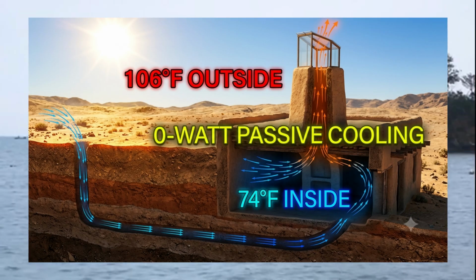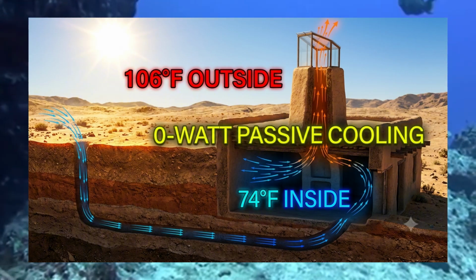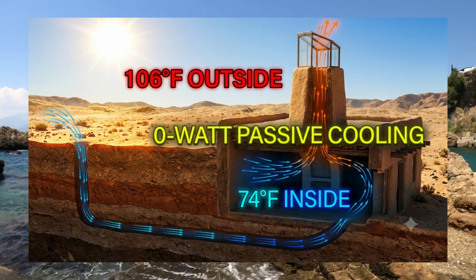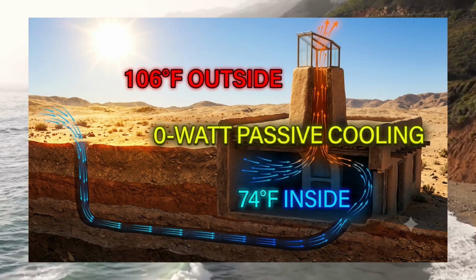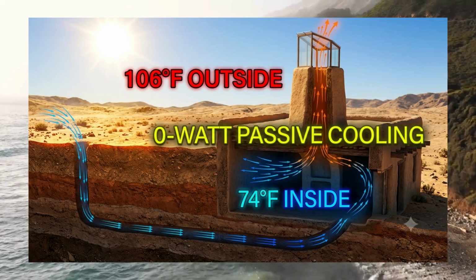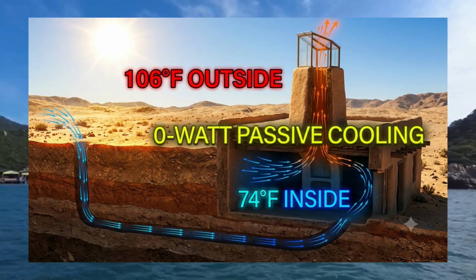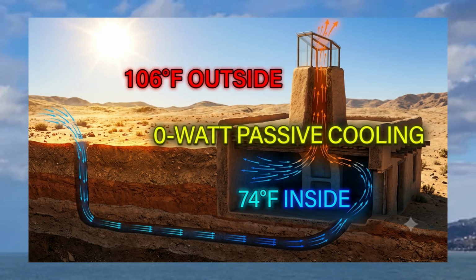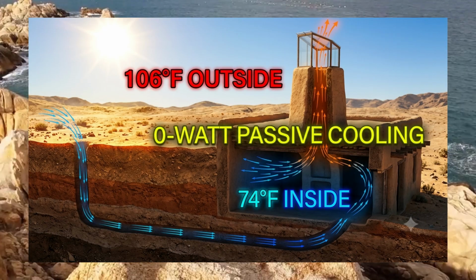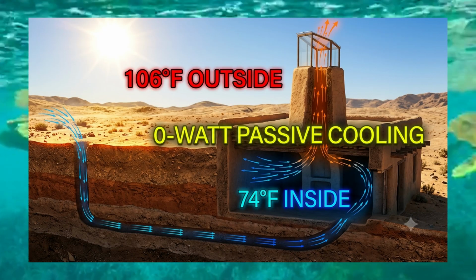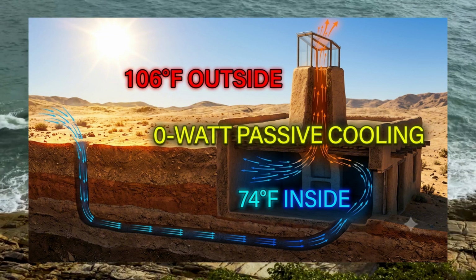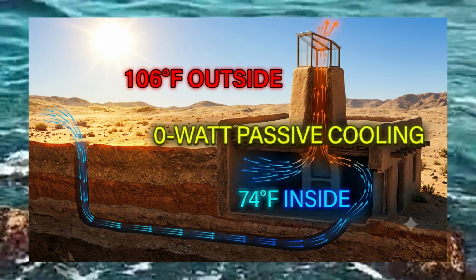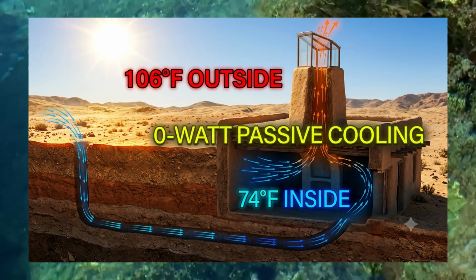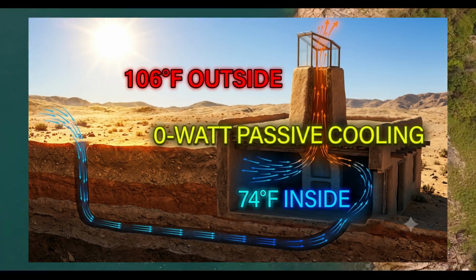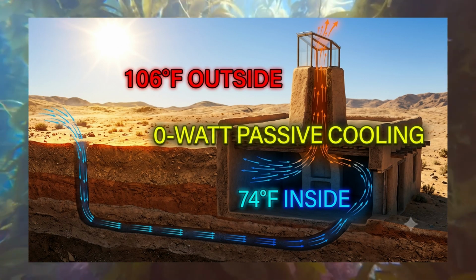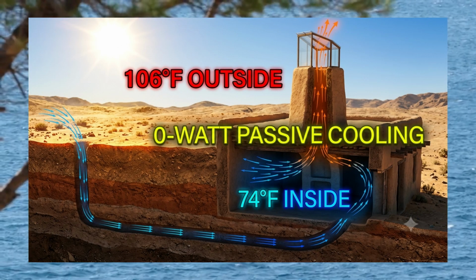This density difference is what drives the stack effect, a phenomenon governed by a simple but powerful mathematical relationship. The pressure difference that drives our draft is determined by the height of the chimney multiplied by the gravitational constant multiplied by the difference between the density of the outside air and the density of the inside air. In simple terms, the taller the chimney and the hotter we can make the air inside it, the greater the pressure differential we create. But this pressure differential is not just pushing air out of the top of the chimney, it is actively pulling air from the base.